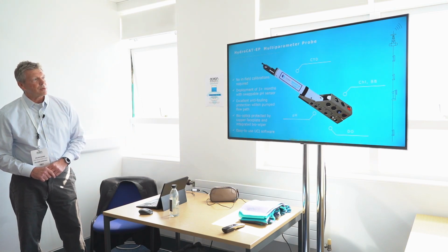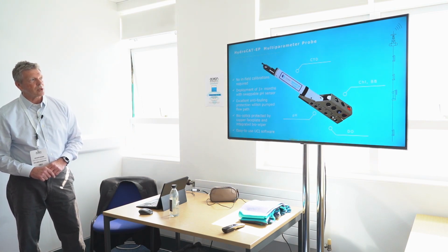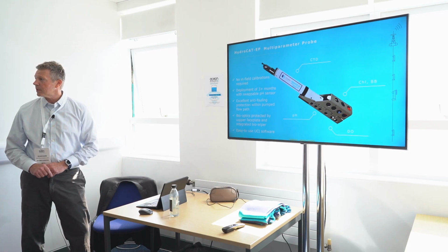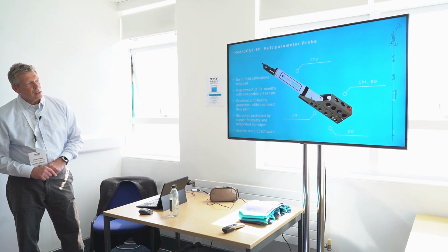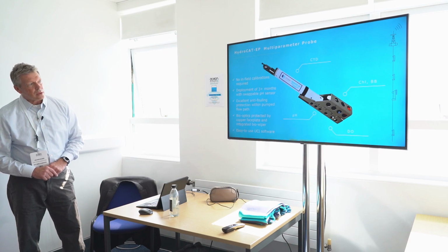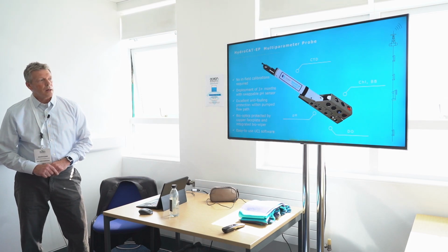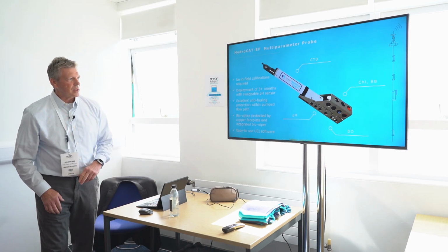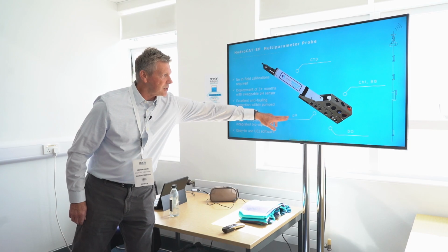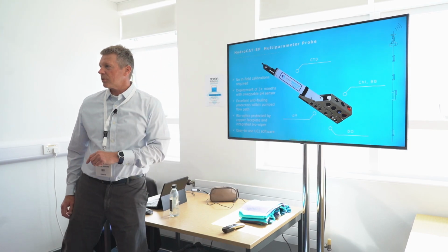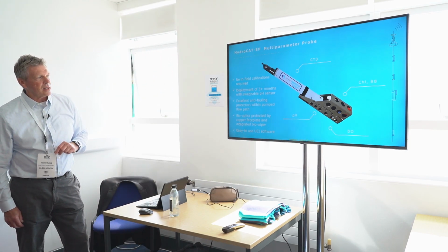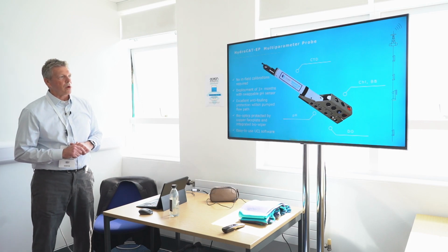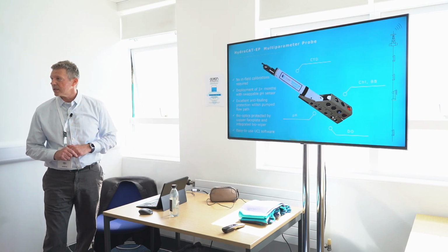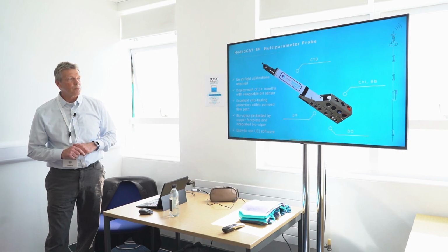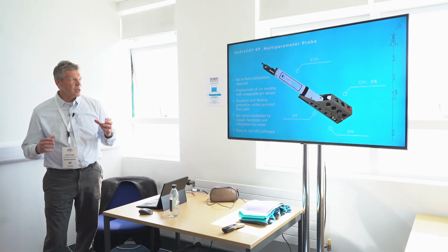So this is the original version. It's very similar to a MicroCAT CTD, if you know what that is, with the CTD and an internally pumped system that includes a DO sensor. You can also see that we managed to integrate a glass ball pH sensing element into that flow path. There's also a 2-parameter chlorophyll fluorescence and turbidity sensor attached to the probe. So it's a really compact system.